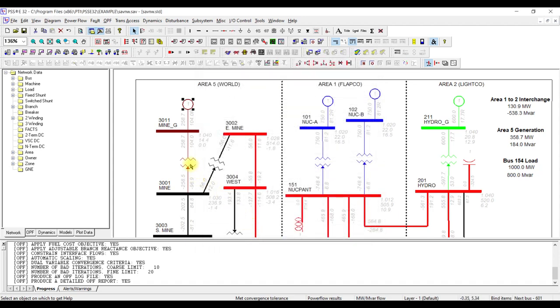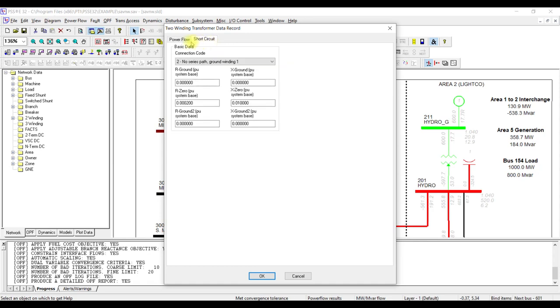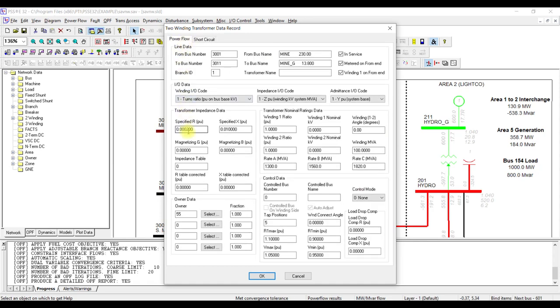If I double-click on the transformer, there you go — same Power Flow and Short Circuit tabs. We are interested in power flow data. Our main concern is with the specified R and X — these two are important. Similarly, we need to adjust the tap as discussed in load flow analysis. The tap can be adjusted here, given in per unit form. So if you want to move the tap up or down, you simply change this value.